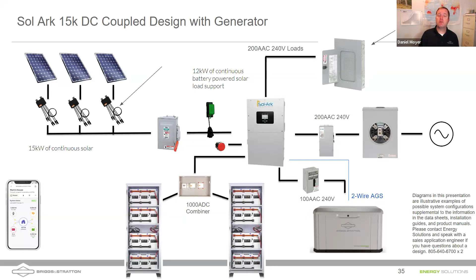There's a small correction to that one. I think we're showing the generator having a 100 amp pass through there, but it's 19.2 kilowatts on the AC side, so I believe that's closer to 80 amps. Still, 80 amps of pass through at 240 volts, you can certainly power most homes with that amount of power. Yeah, that's exactly right. I called it out because the generator has a 100 amp breaker, but it's not capable of that, so you'd want to downsize appropriately. Thank you for that correction.